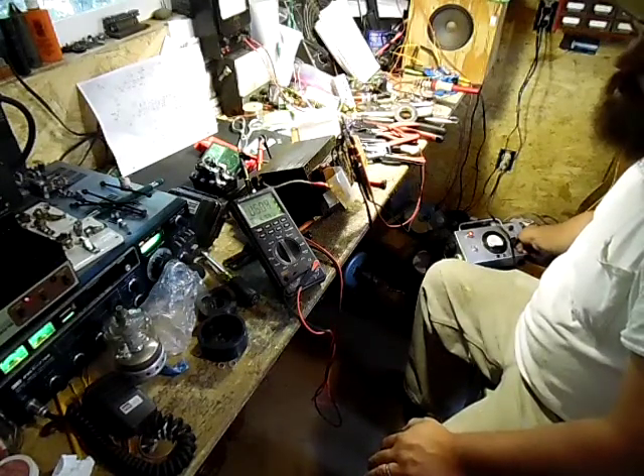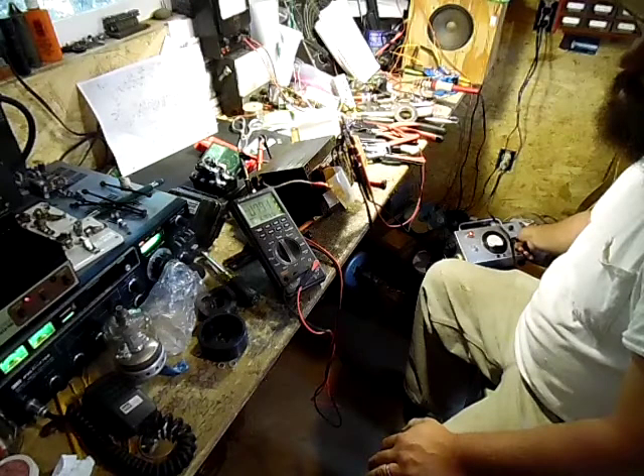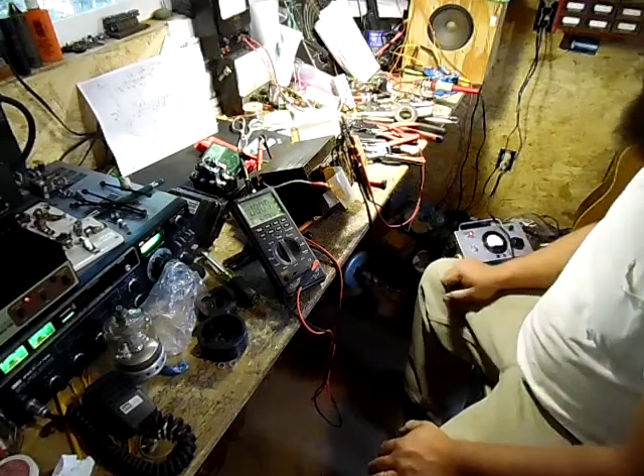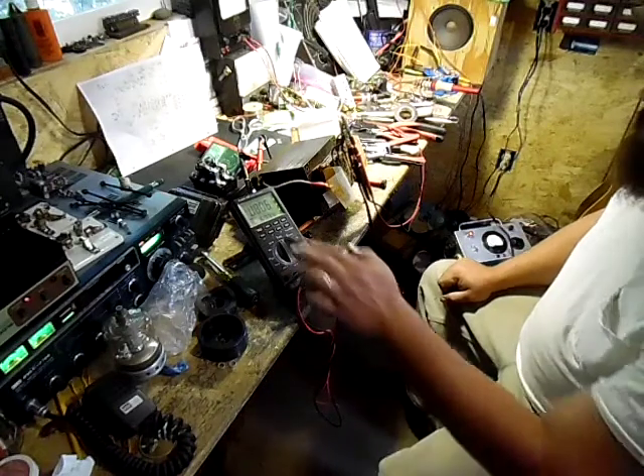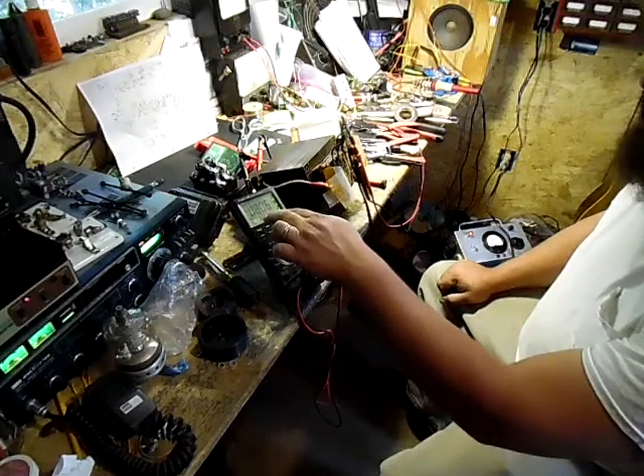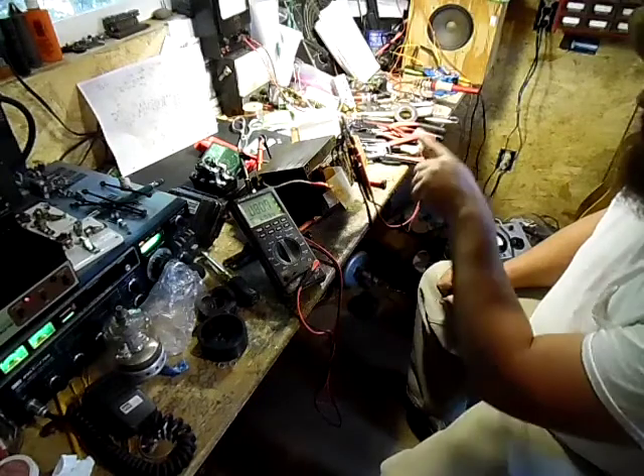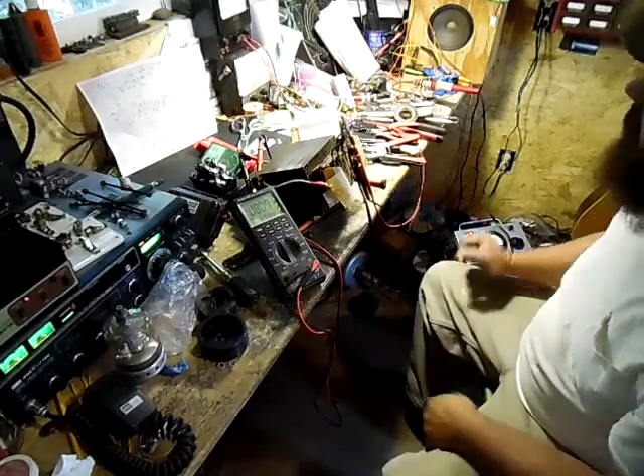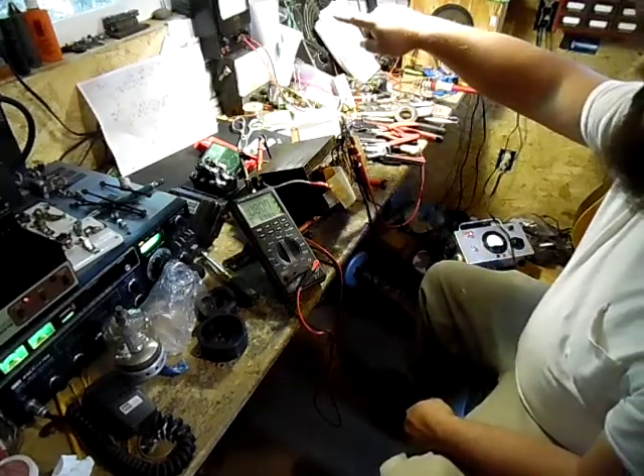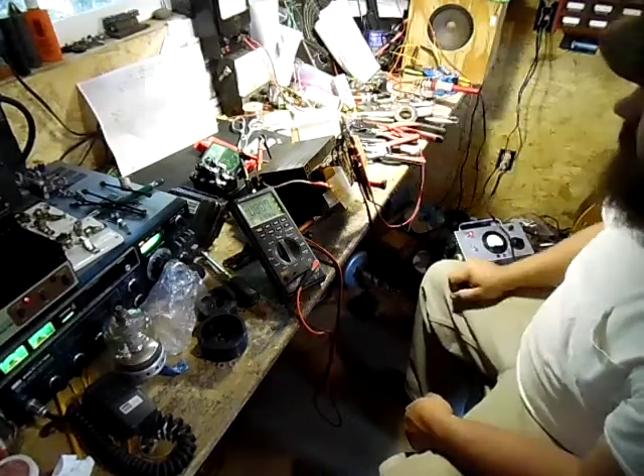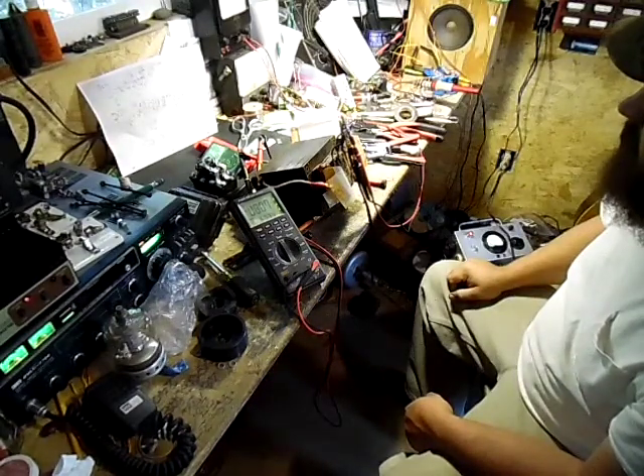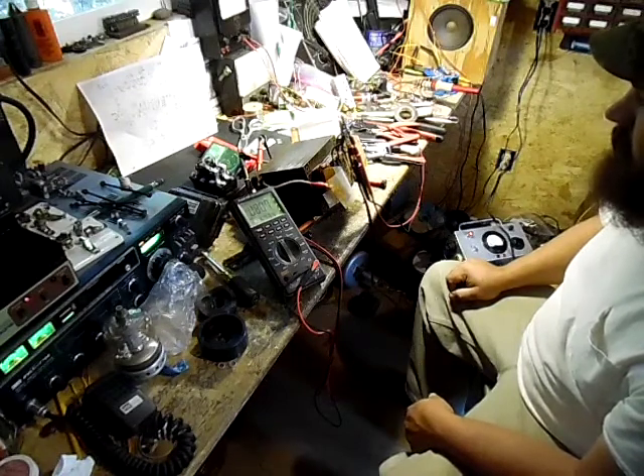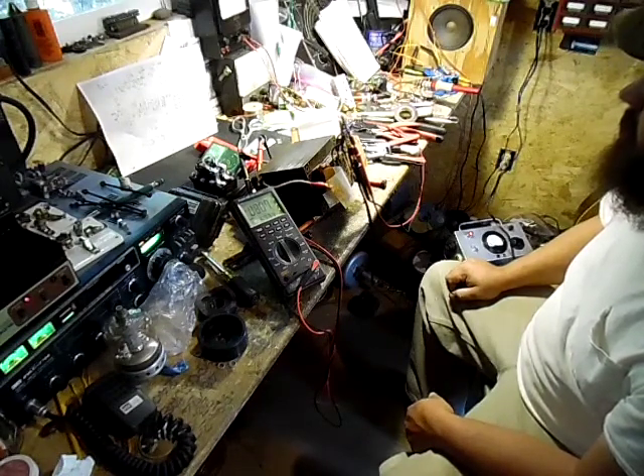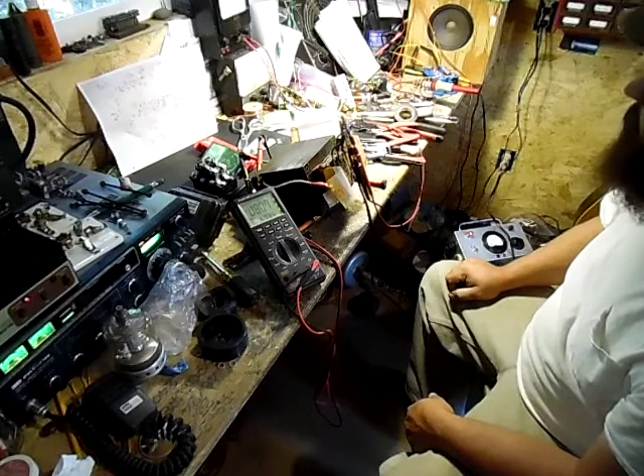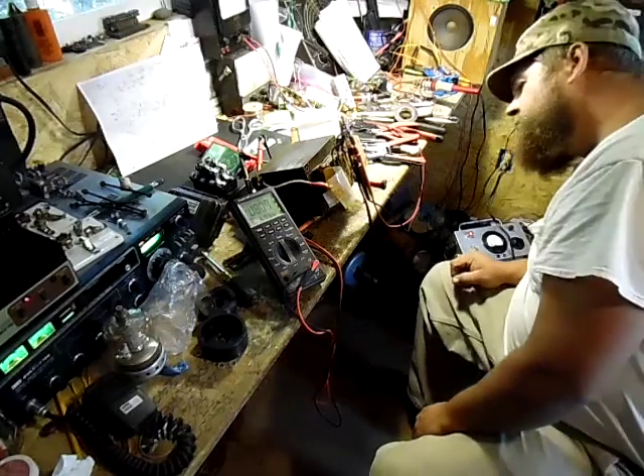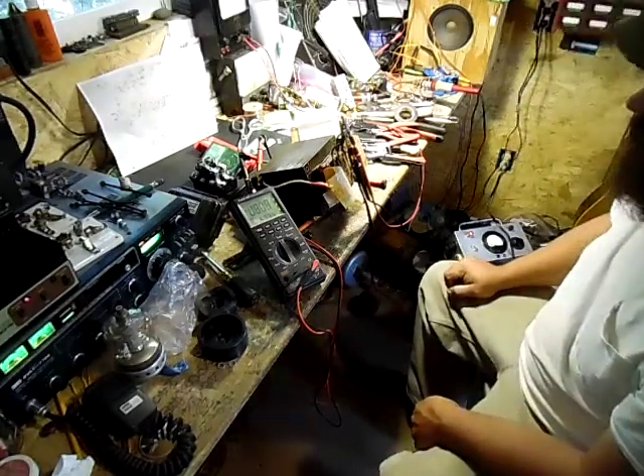All right, so right in there is where it's supposed to be for 120. And I'm showing 806 volts on the high voltage side, with just that one winding being used as the primary. And I'm showing 100 volts coming out of this side here. So it is making voltage, and I'm just going to cap it because it's doing me no good. Yeah, I got no reason for it.